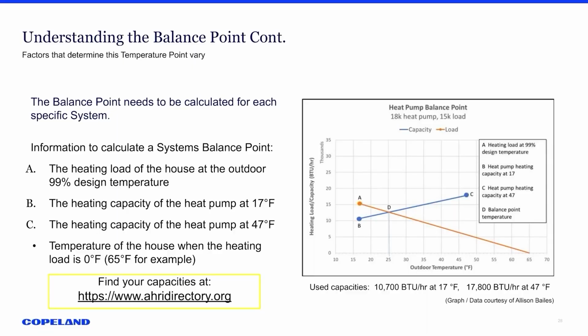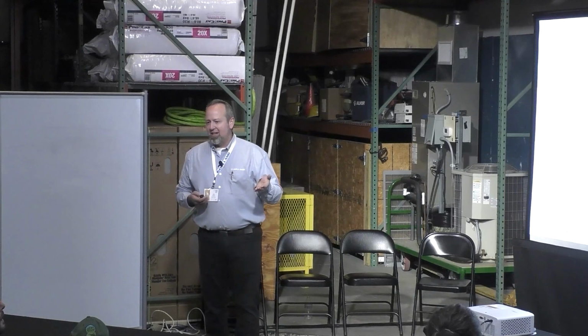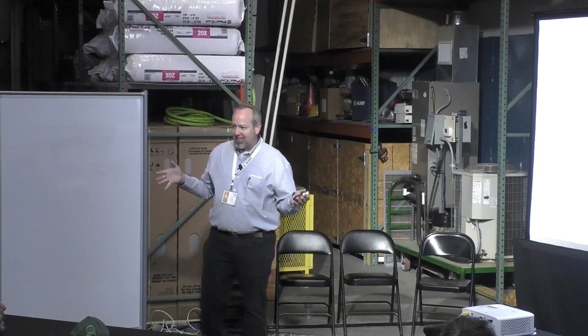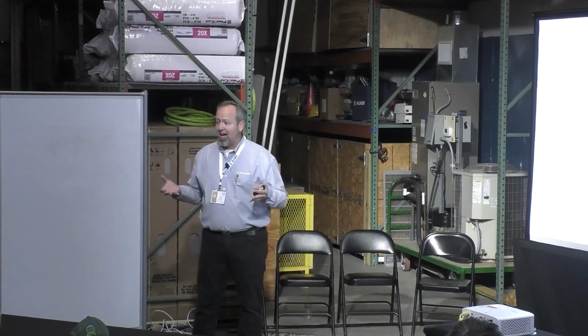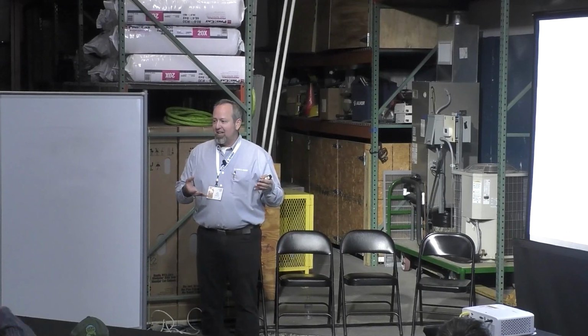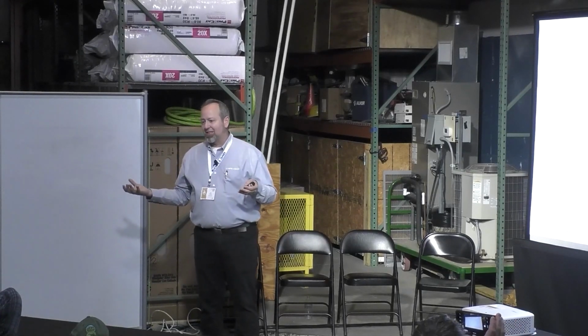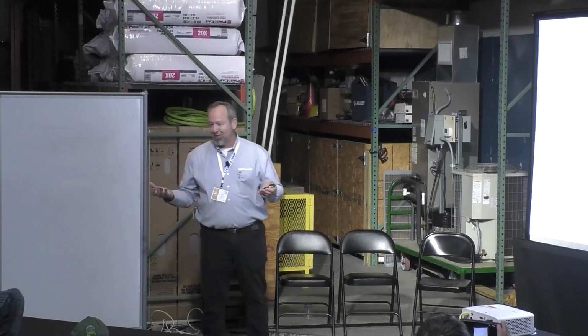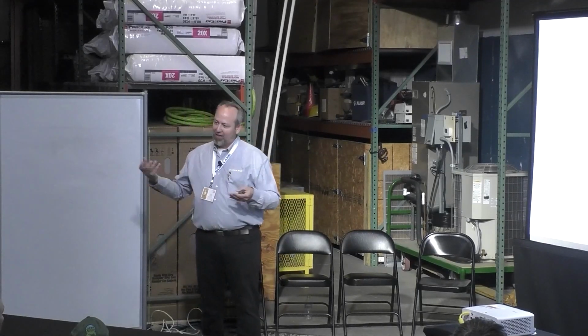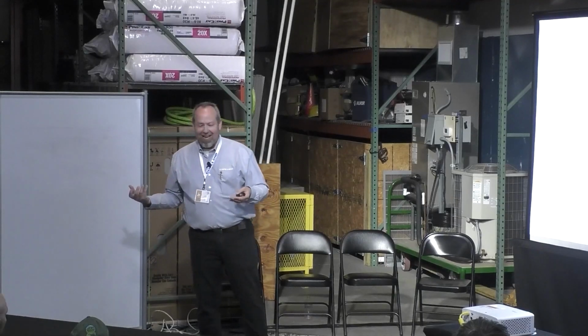So balance point. And what is the balance point? And there's a couple different balance points, and I'm only touching on one of them. There's a second one that I'd encourage you to do a little research if you're curious about. This one is the balance point of capacity, what that heat pump can do. And one of the things that you're looking at when you're sizing things is, I think we heard yesterday, if you size it for the heat capacity and you're way oversized for your cooling capacity, then you're going to have moisture issues within that system, because your cooling capacity is dropping the temperature before it's pulling the humidity out. Your latent's not getting out.